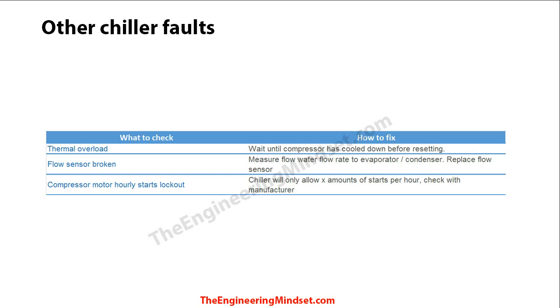Another built-in safety feature is the compressor hourly starts lockout. Manufacturers set a limit on how many times a chiller can start per hour. If loading is very low and the chiller is cycling on and off repeatedly, it will eventually be locked out until the hour resets. This protects the electrical equipment and motor windings from the large inrush current that these chillers draw on startup.